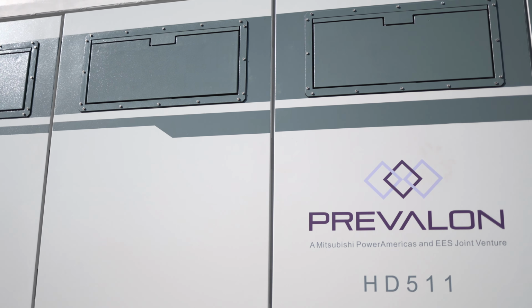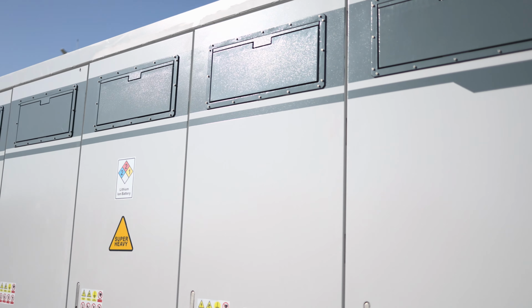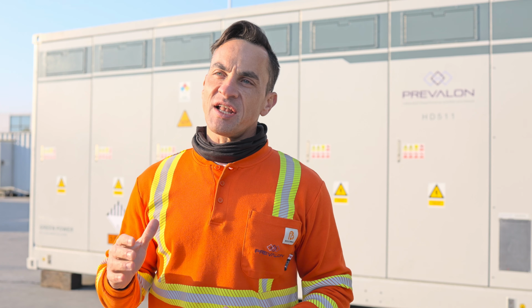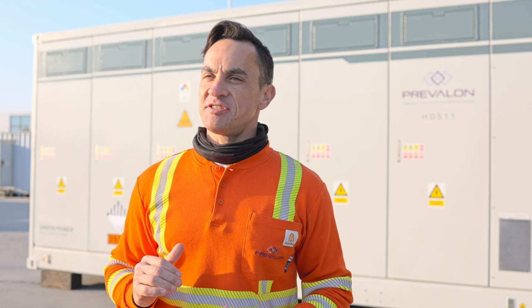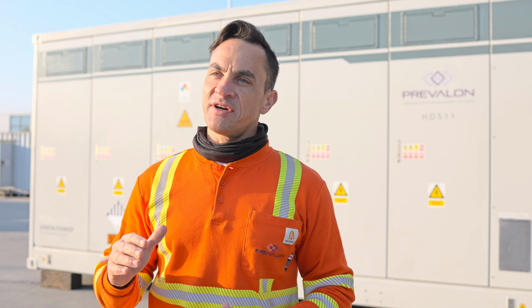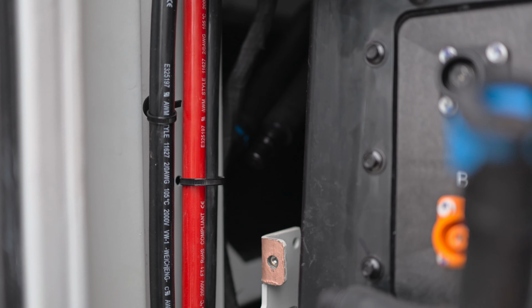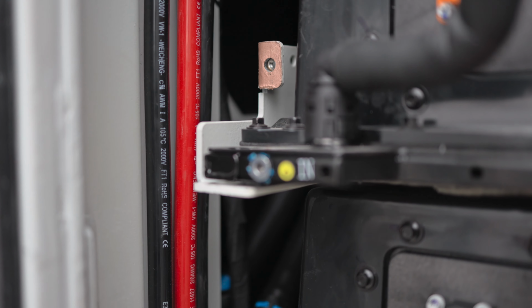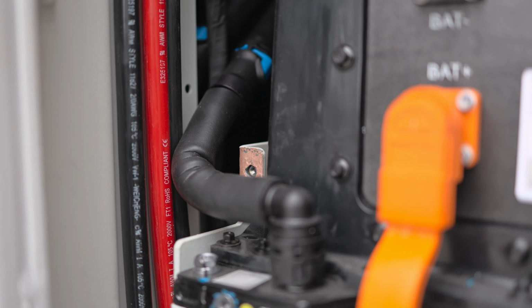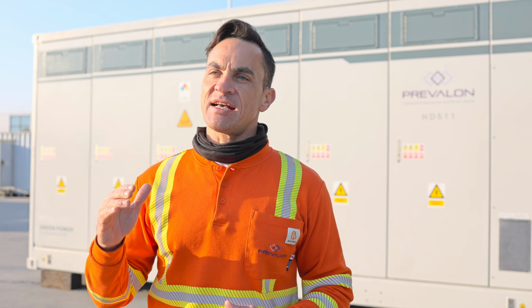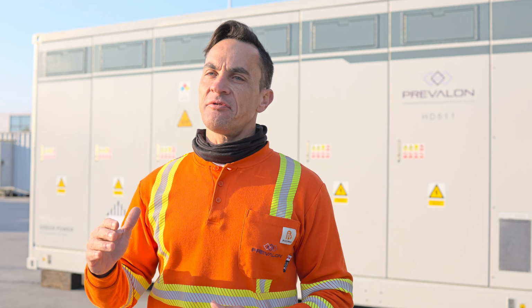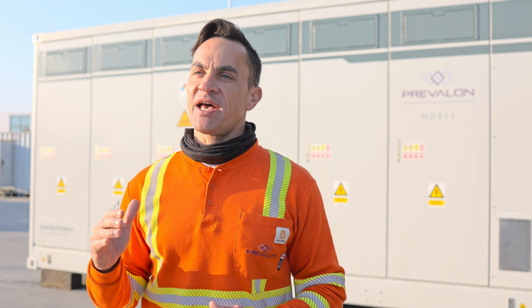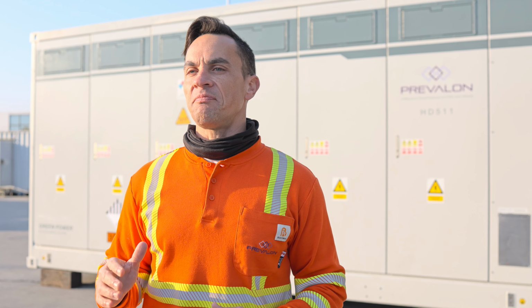Number 4 is remote monitoring. The BMS and enclosure balance of system reports relevant data to the site energy management system. The enclosure monitoring system can provide data up to 24 hours after an auxiliary power interruption. Heat, smoke, and flammable gas sensors are constantly monitored by a site central fire alarm panel that's NFPA 72 compliant.